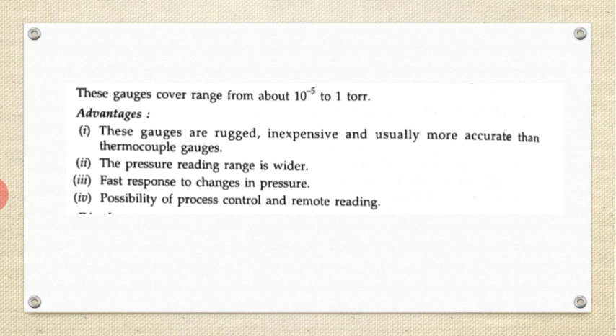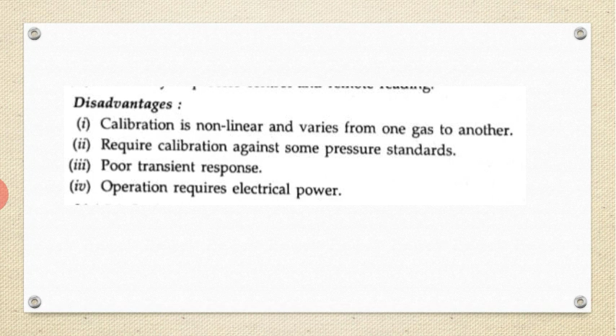And some of the disadvantages: calibration is non-linear and varies from one gas to another, it requires calibration against some pressure standards, poor transient response, and operation requires electrical power. These are some disadvantages related to the Pirani gauge.